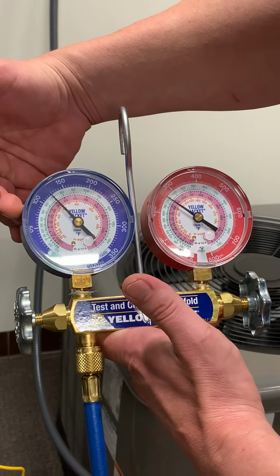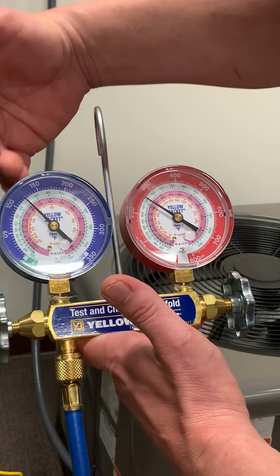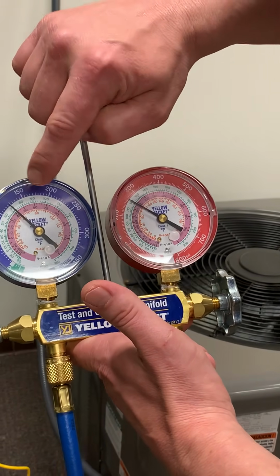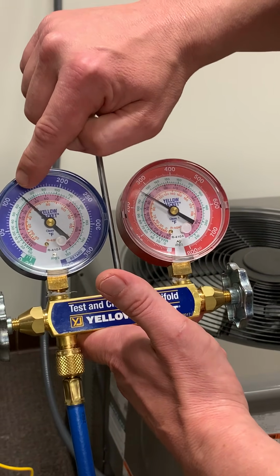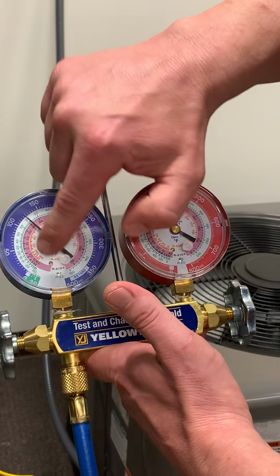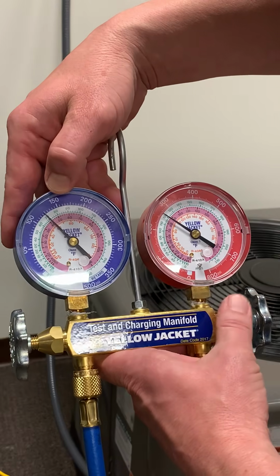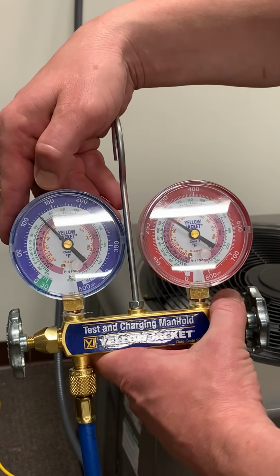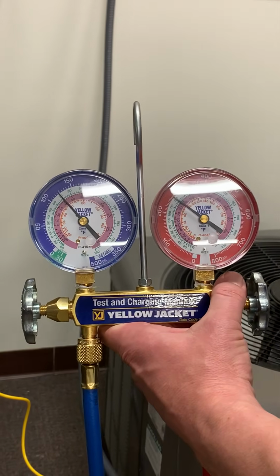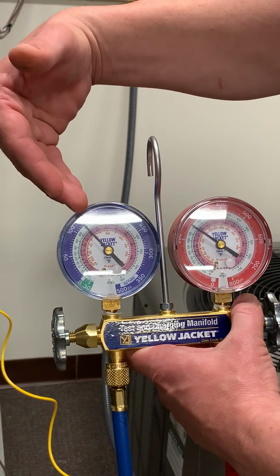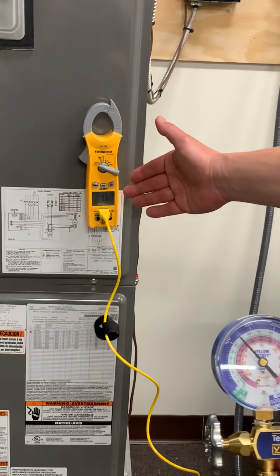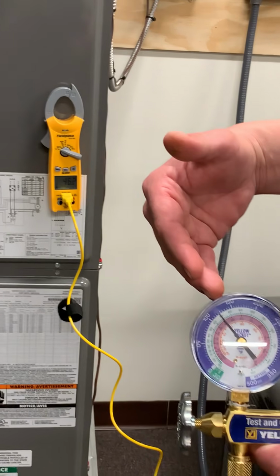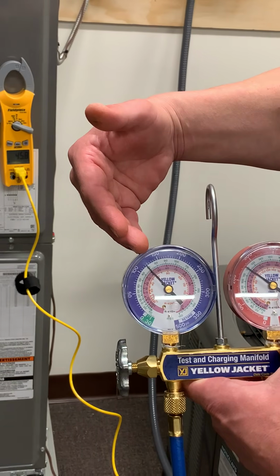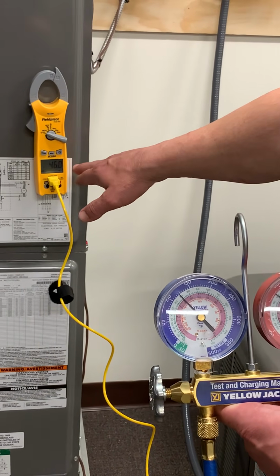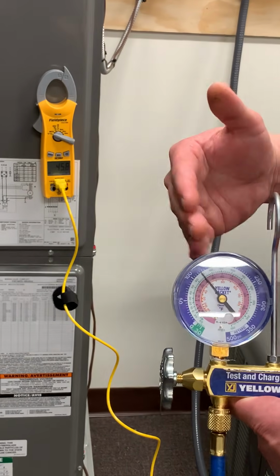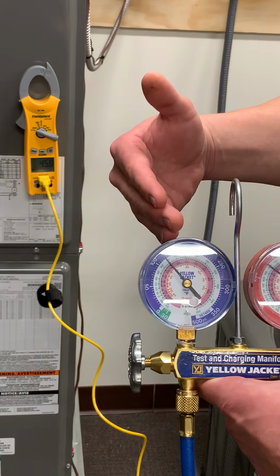And you can see I'm somewhere between 120 and 125 PSI. And if I follow my line down to this inner pink dial, that's where my saturation temperature is. And you can see I'm reading about a 41 degree saturation temperature. So when it comes to superheat, I'm going to take the saturation temperature number and subtract it from my actual line temperature. So I'm reading 41 degrees on my saturation temperature on my gauge, and I'm reading 46 degree line temperature. So 46 minus 41 means I have 5 degrees of superheat.